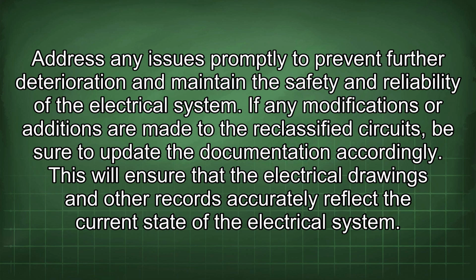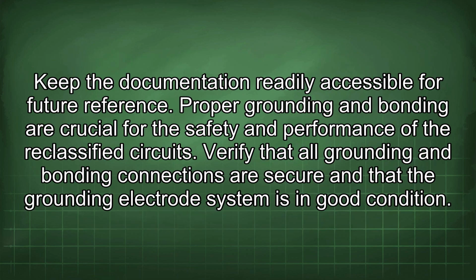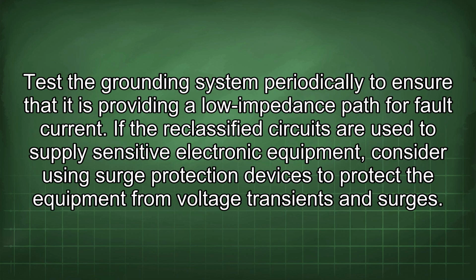This will ensure that the electrical drawings and other records accurately reflect the current state of the electrical system. Keep the documentation readily accessible for future reference. Proper grounding and bonding are crucial for the safety and performance of the reclassified circuits. Verify that all grounding and bonding connections are secure and that the grounding electrode system is in good condition. Test the grounding system periodically to ensure that it is providing a low impedance path for fault current.